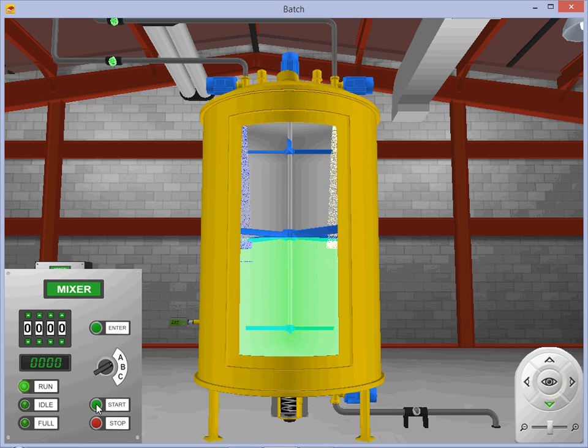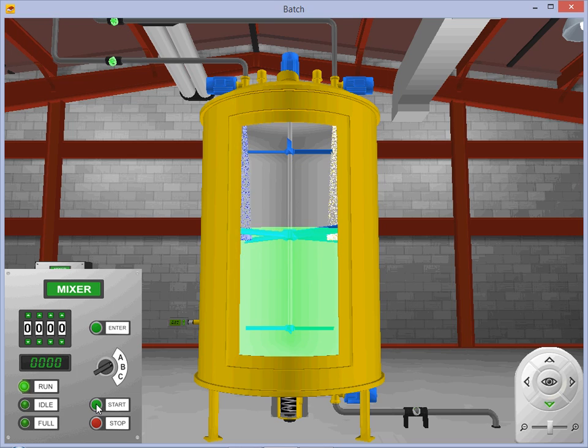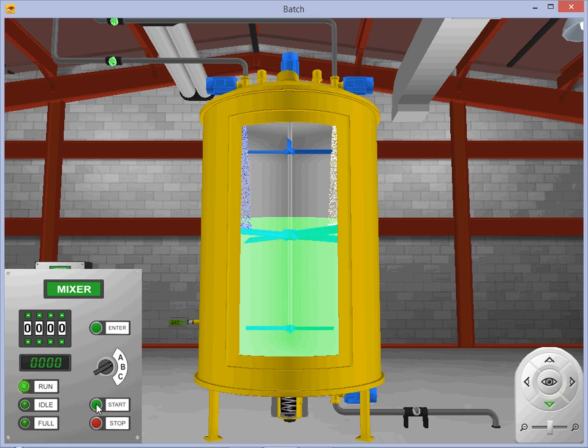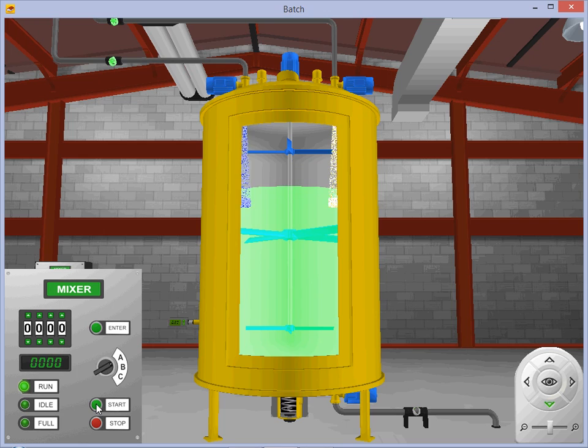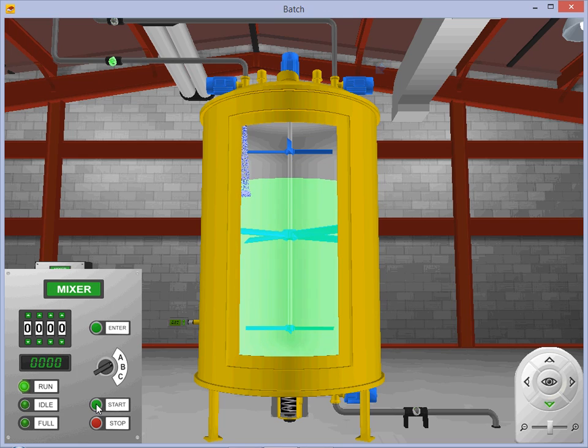Normally open contacts associated with the flow meter inputs are being used to increment the volume tracking counters used in the ladder logic program. Once the desired 10 units of solution B have been added to the tank pump 2 is shut down.